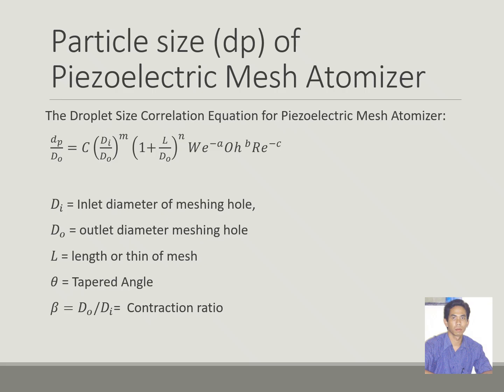In this slide, we present the droplet size correlation equation for a piezoelectric mesh atomizer, which is used to predict the particle or droplet diameter generated during atomization. The equation shown here expresses the normalized droplet size, dp per dO, as a function of geometrical parameters of the mesh and dimensionless fluid dynamic numbers. This correlation helps us understand how both device design and fluid properties influence droplet formation.